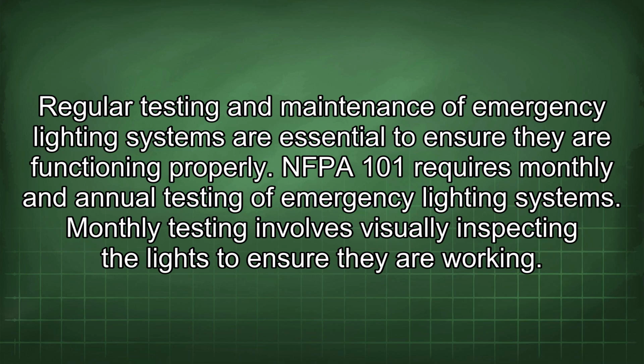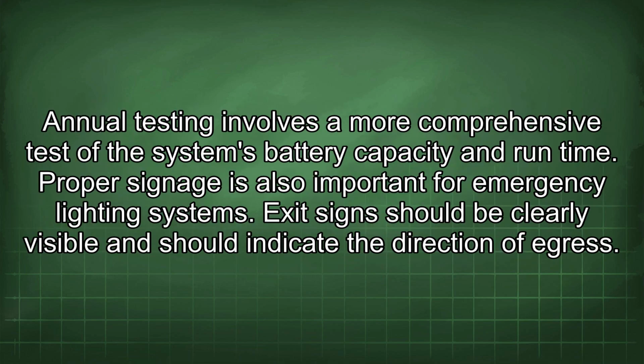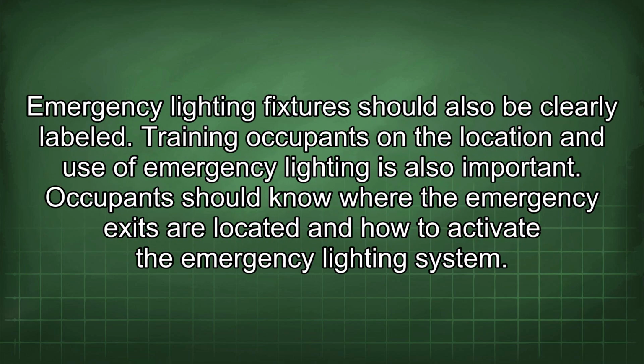NFPA 101 requires monthly and annual testing of emergency lighting systems. Monthly testing involves visually inspecting the lights to ensure they are working. Annual testing involves a more comprehensive test of the system's battery capacity and runtime. Proper signage is also important for emergency lighting systems. Exit signs should be clearly visible and should indicate the direction of egress. Emergency lighting fixtures should also be clearly labeled.